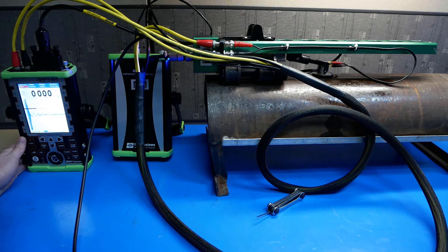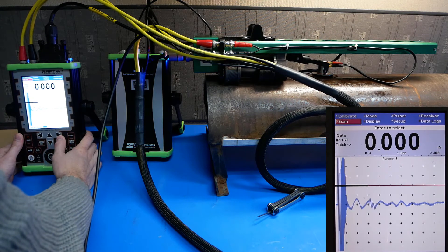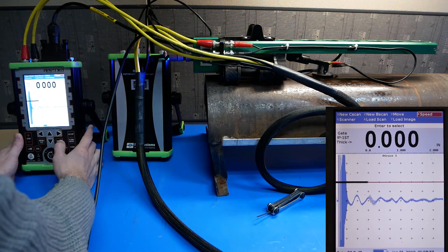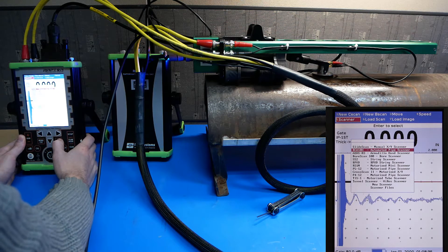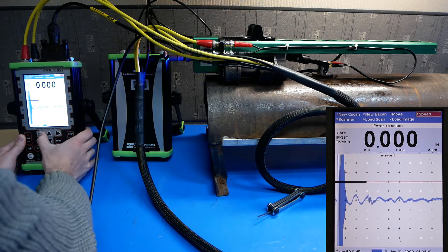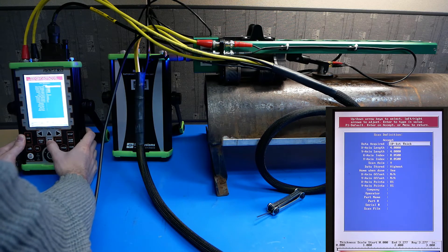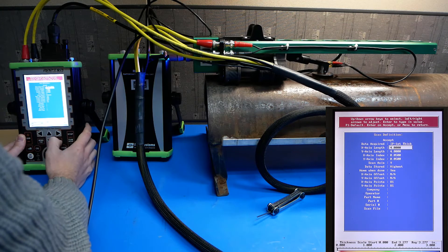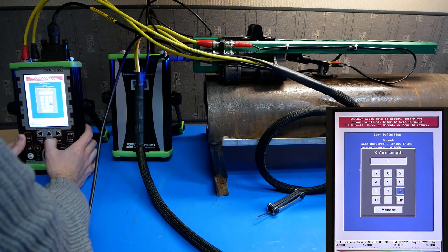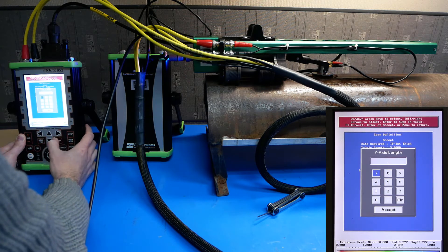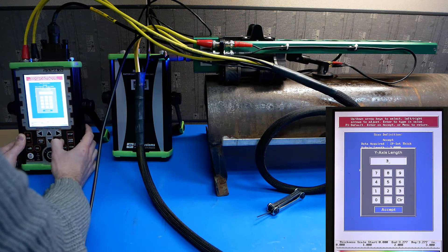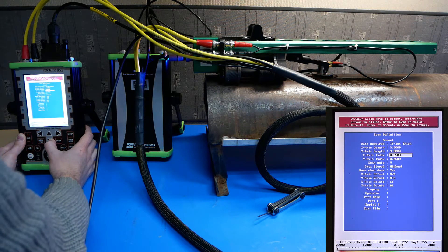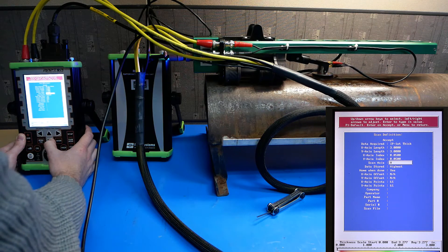Now, to set up this for a scan, you go from the main menu, scan, you go to scanner, make sure we have RCA 10 connected. Go to new C scan and set your scan area. I'll set it to 3 by 3 inches. 3 inches on the X axis, 3 inches on the Y axis. I'll keep my increment values the same and I'll raster along the Y axis.